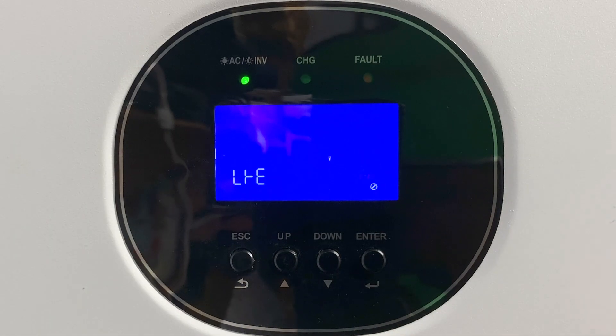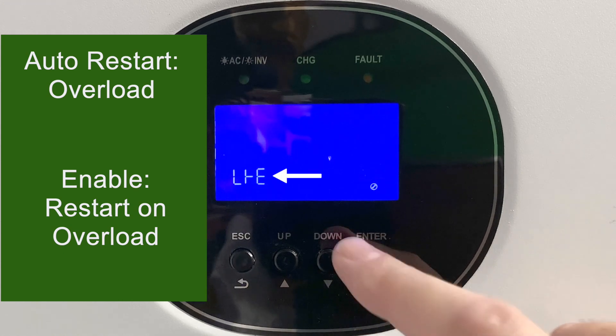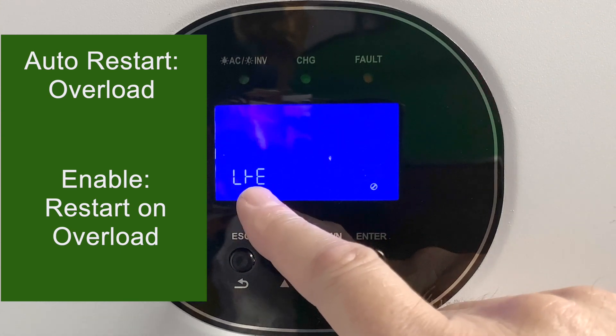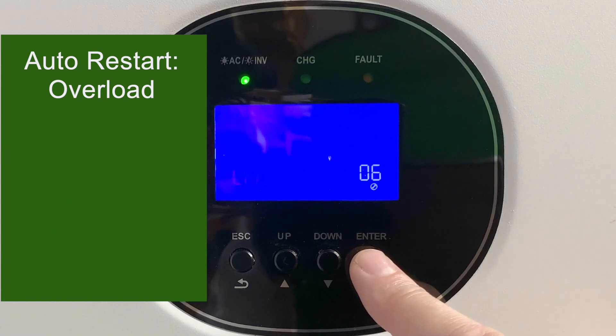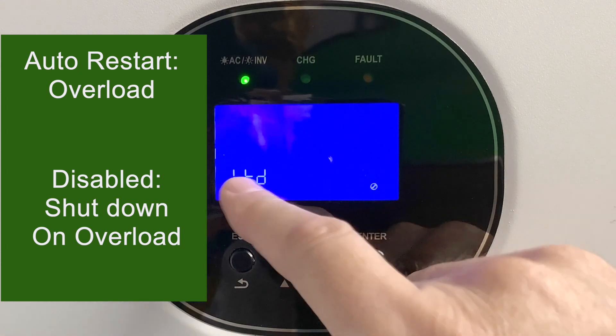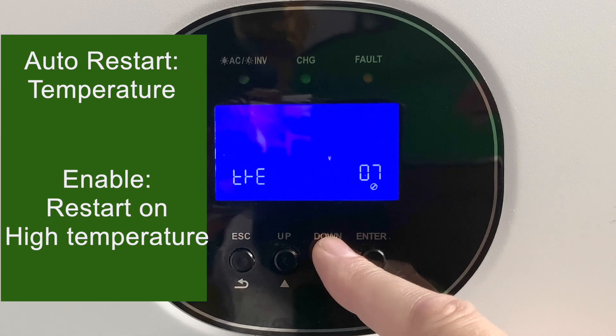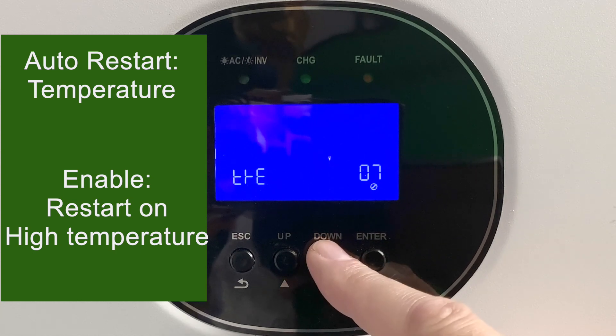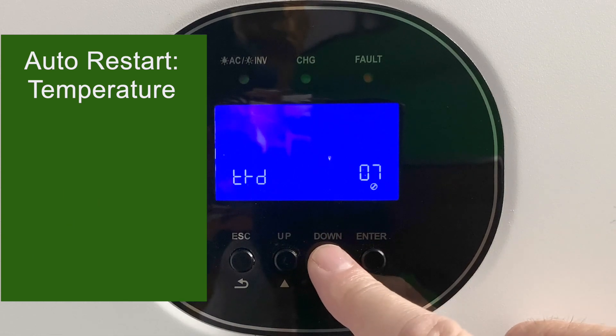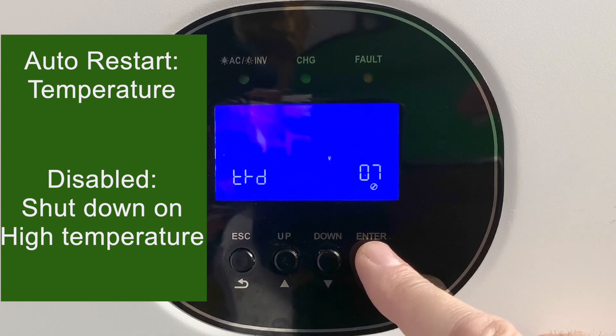Setting number six relates to overload auto-restart. If the setting ends in E, it's enabled, meaning the Growatt inverter will restart if it overloads. If it ends in D, auto-restart is disabled and the Growatt will shut itself down on an overload. Setting number seven is very similar but is about temperature. With E, it will auto-restart if the temperature gets too high. With D, the Growatt inverter will shut down on a high temperature.